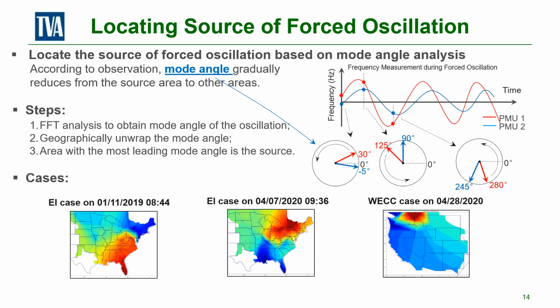So locating the source of forced oscillation, or even regular oscillation, is important. That's very interesting research carried out by different groups using different approaches. But none of the groups can do anything without time-synchronized measurement. It can be phasor, like angle and magnitude, or it can just be a waveform record. Either one is possible. The reason people use phasor is because our power grid, our large grid, was mathematically designed to be easily computed or controlled in terms of phasor. Now when you have IBRs, you have a lot of fast phenomena, and phasor would be too slow, so you may need point-on-wave, or just take the waveform directly.